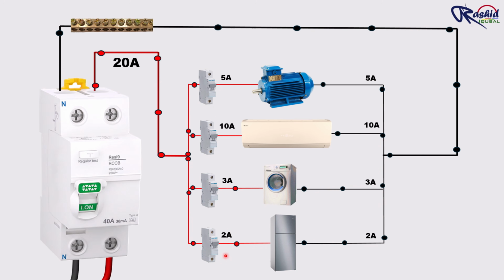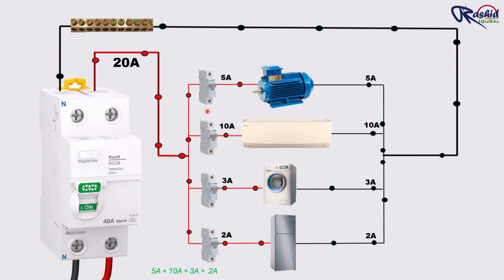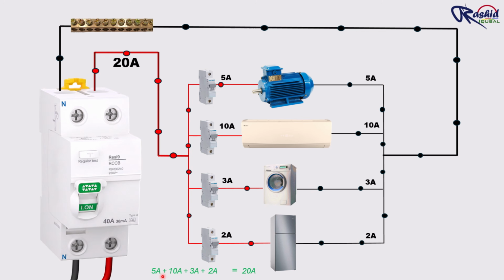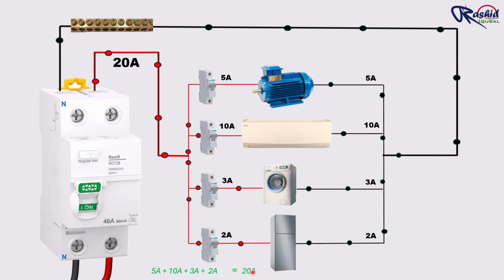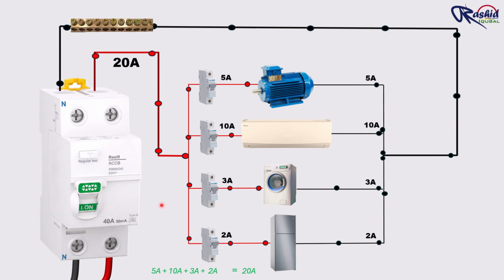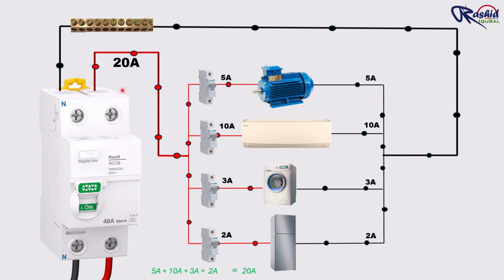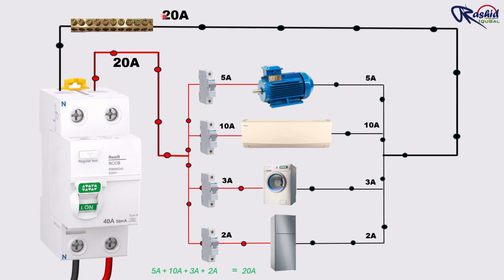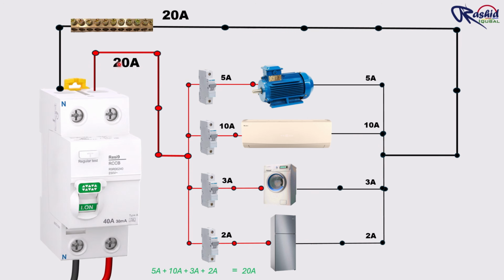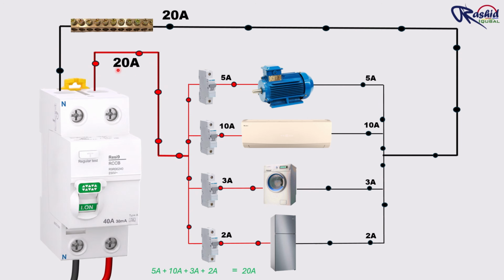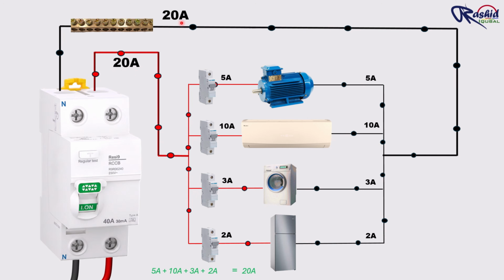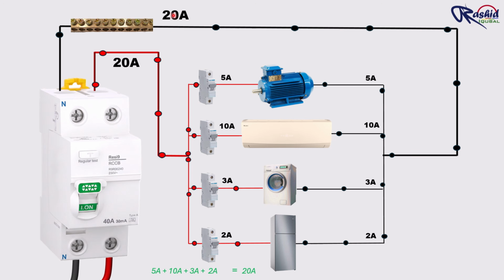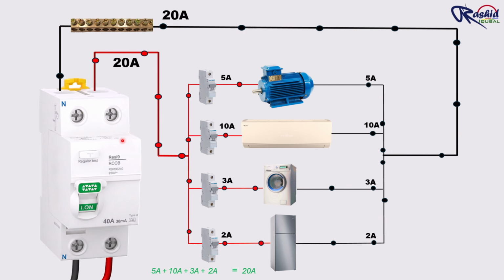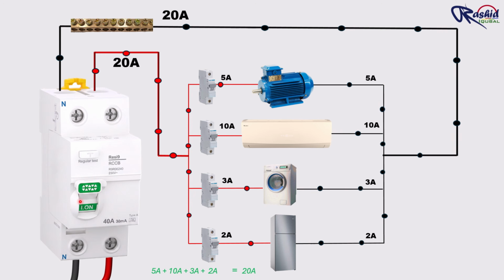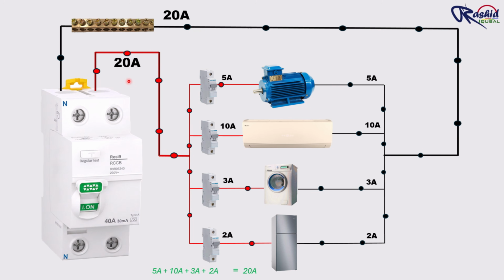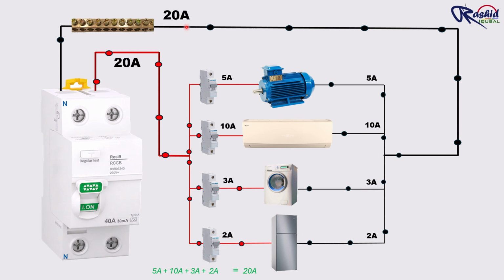So the total current flowing through the phase conductor is 20 ampere. After adding all these current ratings, it becomes 20 ampere. Now remember one important practical point. Whatever amount of current goes through the phase wire, the same amount of current must return through the neutral wire. So in this case, phase current is 20 ampere, so the neutral current will be 20 ampere as well. Since both currents are exactly equal, the RCCB detects a balanced condition and keeps the circuit on. Here you can see 20 ampere is going through the phase wire and 20 ampere returns through the neutral wire.